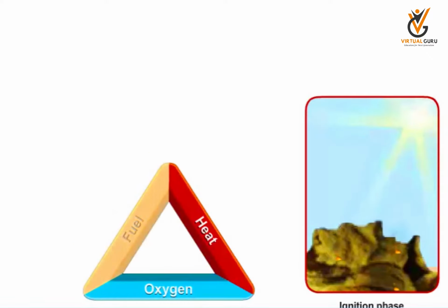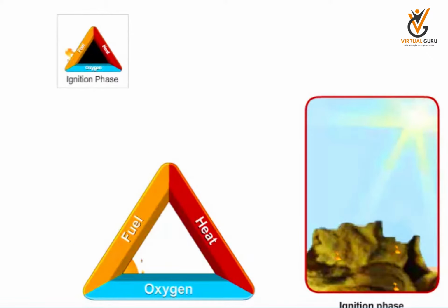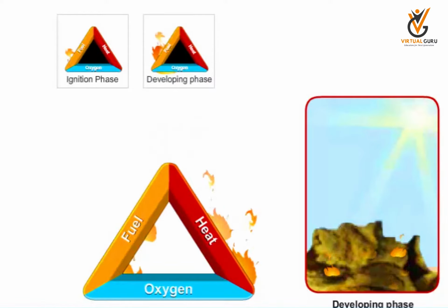Ignition phase. When there is sufficient air-vapor mixture and the temperature of the substance exceeds its ignition point, the fire starts. This fire can be due to an external heat source, autoignition, or spontaneous ignition. Spontaneous ignition occurs when certain materials become warm during oxidation, producing more heat, which accelerates the oxidation process. In the ignition or incipient phase, heat flows back to the material due to radiation. It results in a chain reaction, enabling the components to sustain fire.